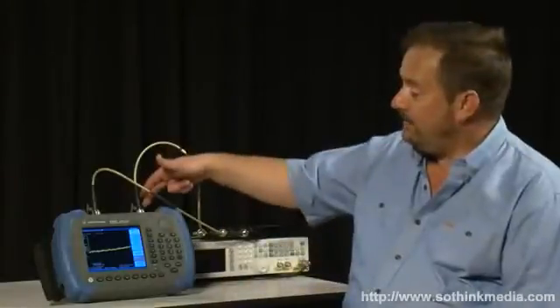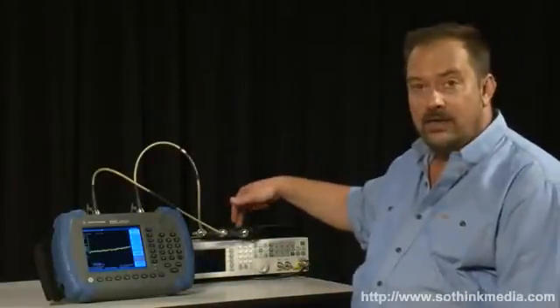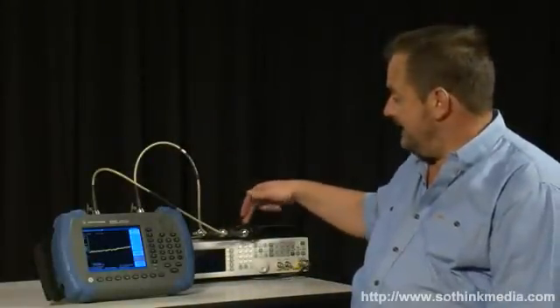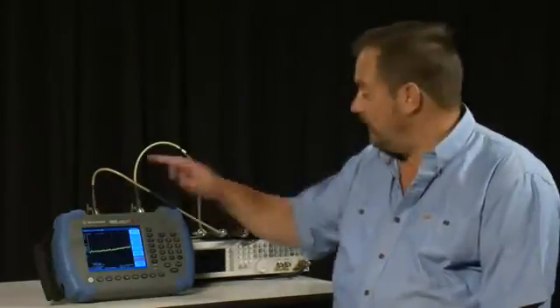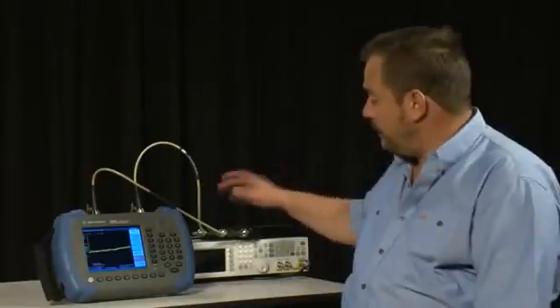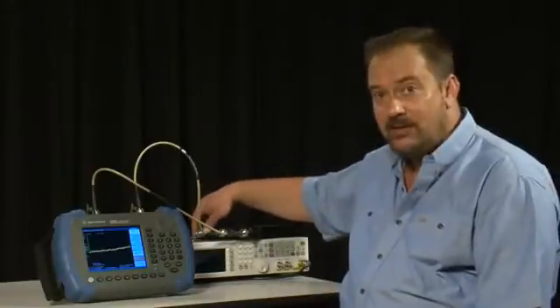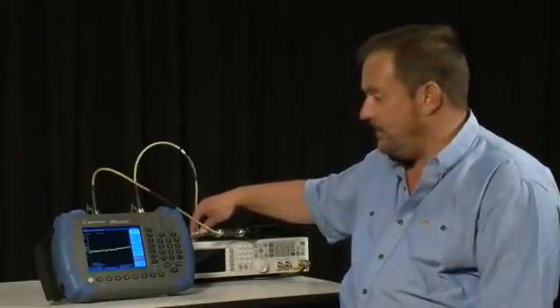So I have connected the tracking generator output to one of the inputs on the filter, and the output from the filter to the input of the spectrum analyzer. Now, don't forget, if you are measuring a three port device such as this, remember to terminate any unused ports with a 50 ohm load.